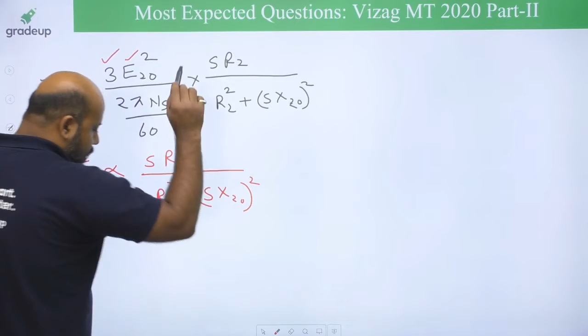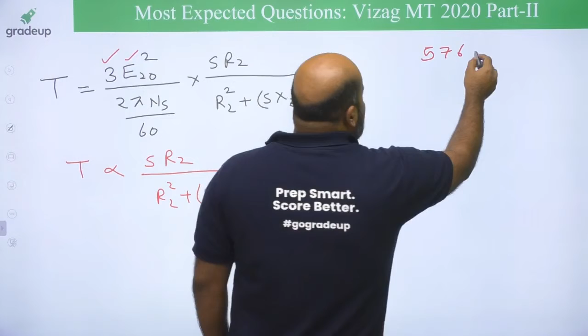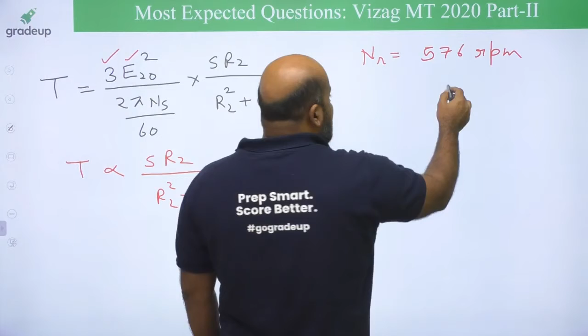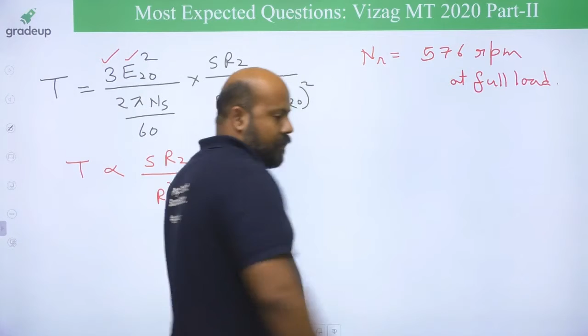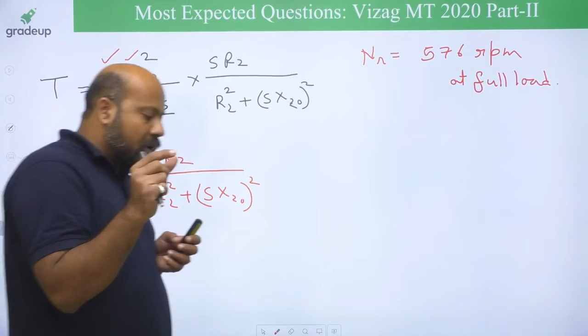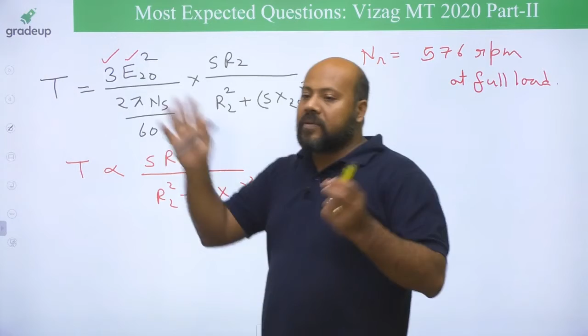Now you see the speed. The speed is given as 576 RPM at full load. Yes or no? Now, one thing you must know about the induction motor is that from no load to full load, the speed is normally very close to, just behind, the synchronous speed. The slip is mostly a very, very small value. Slip cannot be a large value. If slip is large, there is going to be too much heating in the induction motor. We do not want that condition. Without slip, the motor is not going to operate, but still the slip is a very, very small value.